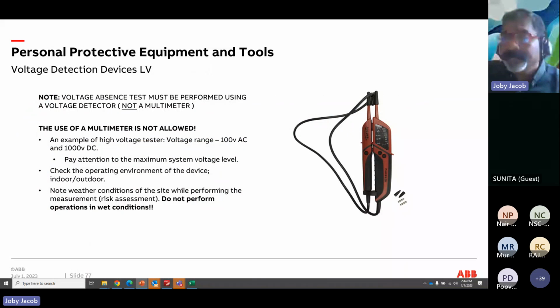So, voltage detectors. We are not supposed to use multimeters, because multimeters are a measuring device, and there are a lot of cases where you use the multimeter and you are taking the measurement and somebody behind holds the multimeter and suddenly changes to continuity. Then if it's measuring, you are in big trouble, right? So multimeters are considered a measuring device. We use voltage detectors so that such things should not happen.